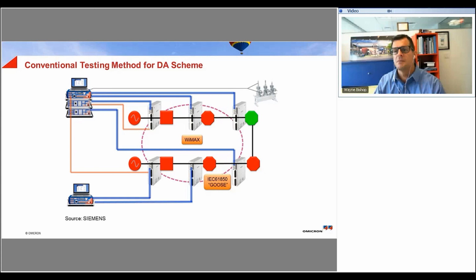Scheme testing can be extremely complex and may require weeks to months. For every type of fault scenario, load and fault values for each operating state must be calculated for every single recloser in the scheme in order to simulate realistic faults. Then for the execution of each test case, local coordination to turn on test injection or an IRIG-B signal, or any kind of coordination for specific designated times, is needed to simulate each step of the test case. Any kind of mistake or miscommunication amongst any of the test personnel would then result in an inaccurate test. Then, after execution, the results from each of the locations must be collected, merged, and assessed, matching up all the different timestamps. Then, after all this is done, if any issues are discovered, the automation logic would need to be adapted in order to address the problems.